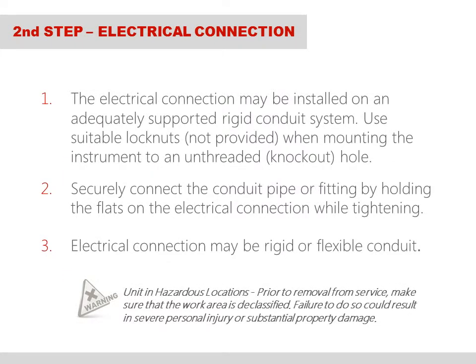The final step in the installation process is the electrical connection. As noted on the previous slide, it is important to avoid the use of a pipe wrench, monkey wrench, channel lock, vice grip, or similar style tools on the 815's housing. The 815 has a high quality, laser etched, 26 gauge stainless steel nameplate or tag that could be damaged or separated from the housing by these tools. Furthermore, the very important external ground lug could be damaged as well.